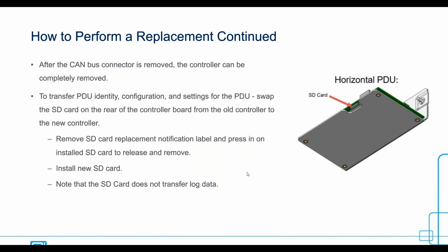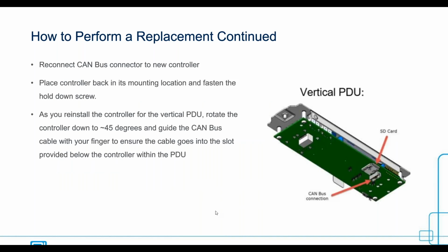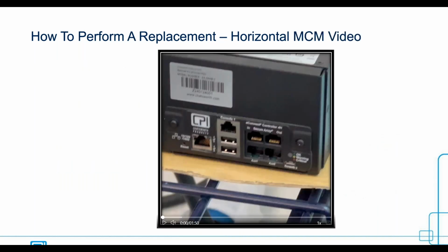Now it's safe to reconnect the CAN bus connector to the new controller, and make sure to adjust the cable with your finger so it goes in the slot. Finally, set the MCM back into the PDU chassis by holding it down and placing the screw or screws back. To demonstrate this, we have prepared a few mock videos, and first we will show the horizontal.